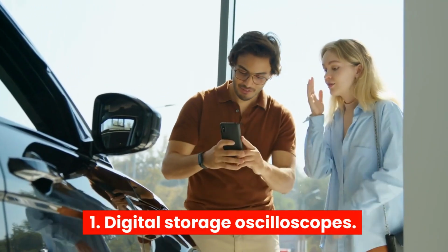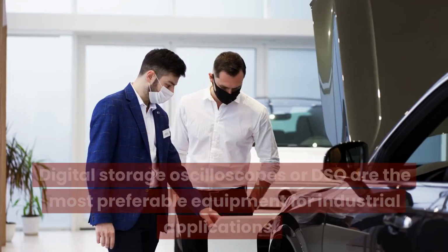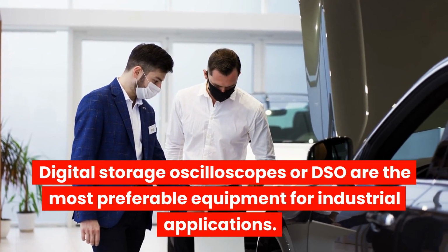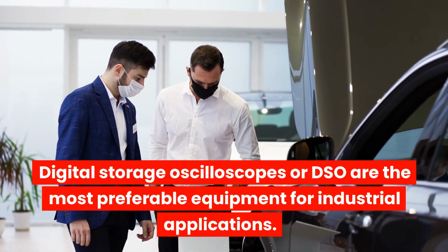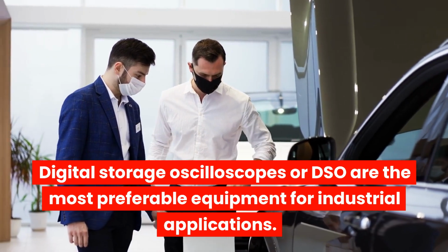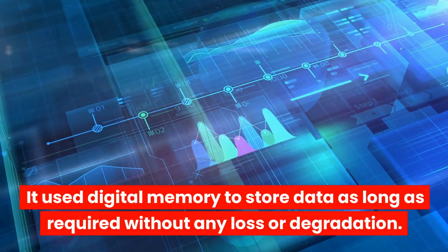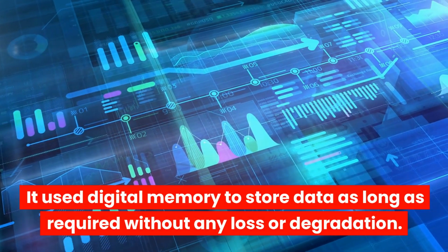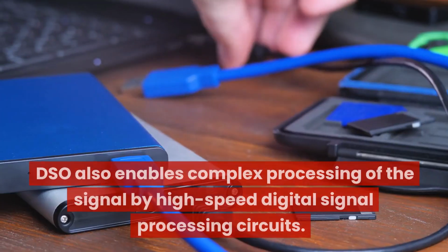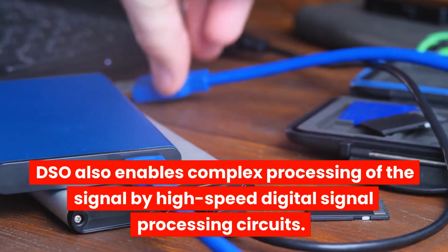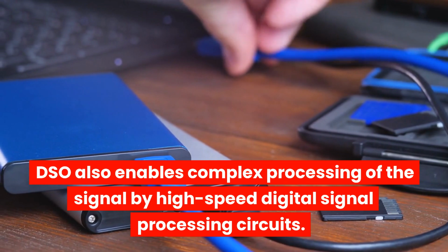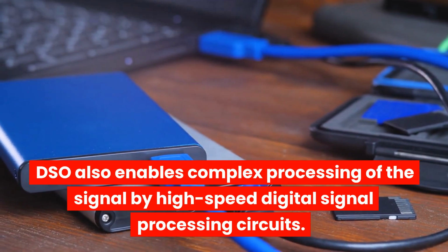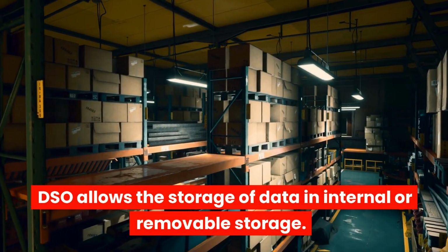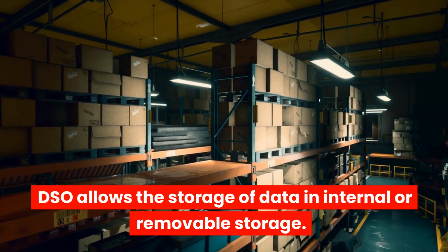1. Digital storage oscilloscopes. Digital storage oscilloscopes, or DSO, are the most preferable equipment for industrial applications. It uses digital memory to store data as long as required without any loss or degradation. DSO also enables complex processing of the signal by high-speed digital signal processing circuits. DSO allows the storage of data in internal or removable storage.